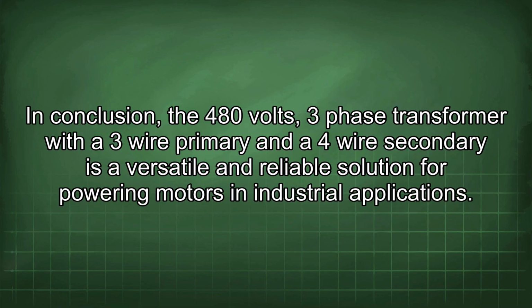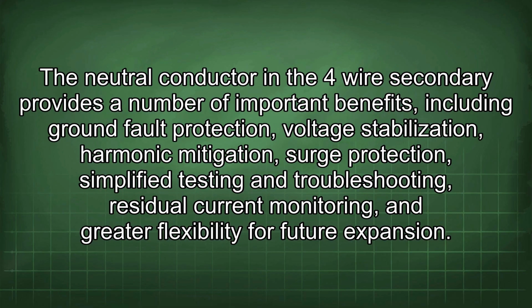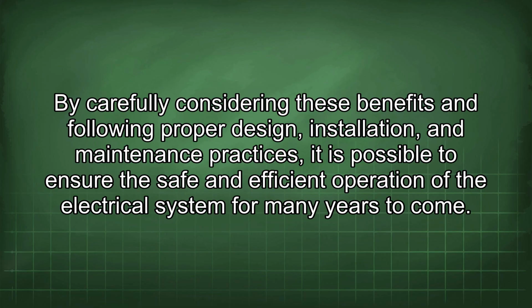In conclusion, the 480 volts 3-phase transformer with a 3-wire primary and a 4-wire secondary is a versatile and reliable solution for powering motors in industrial applications. The neutral conductor in the 4-wire secondary provides a number of important benefits, including ground fault protection, voltage stabilization, harmonic mitigation, surge protection, simplified testing and troubleshooting, residual current monitoring, and greater flexibility for future expansion. By carefully considering these benefits and following proper design, installation, and maintenance practices, it is possible to ensure the safe and efficient operation of the electrical system for many years to come.